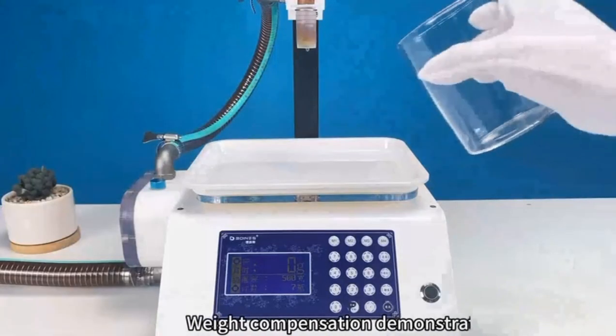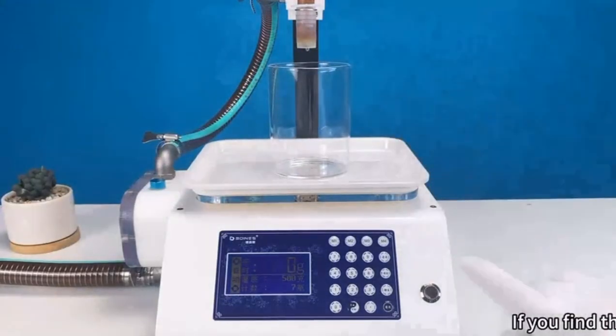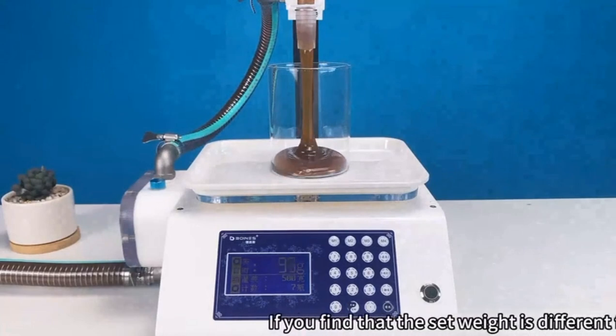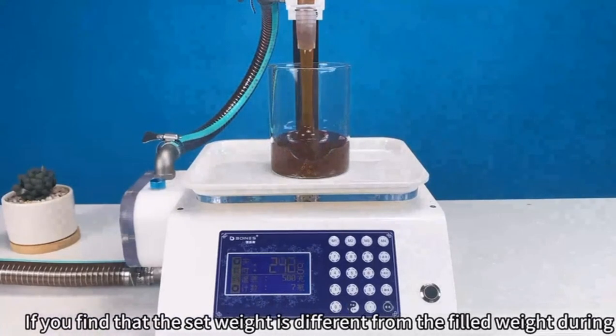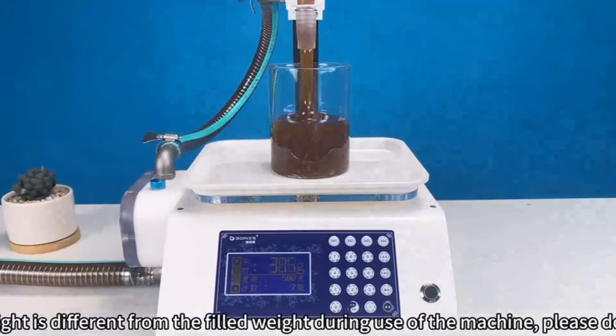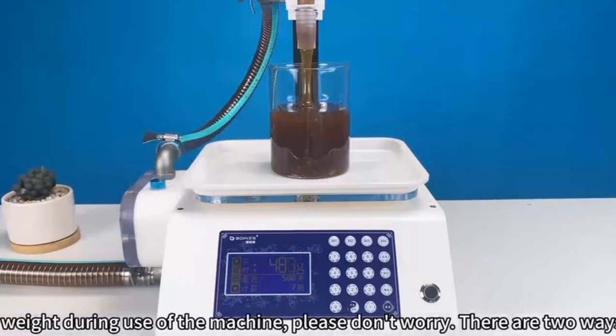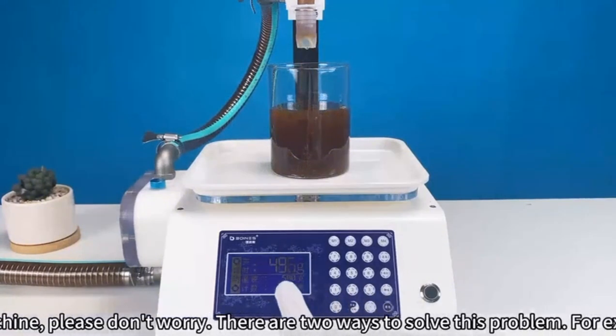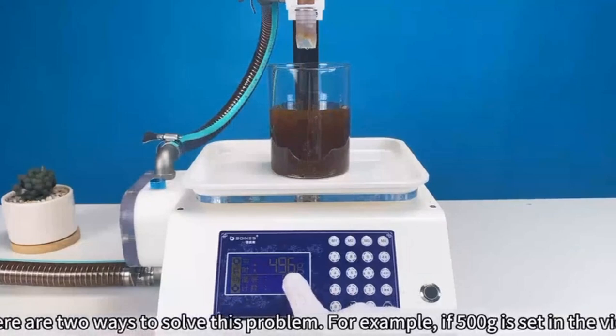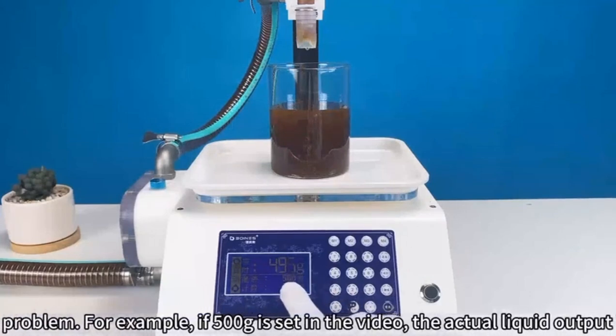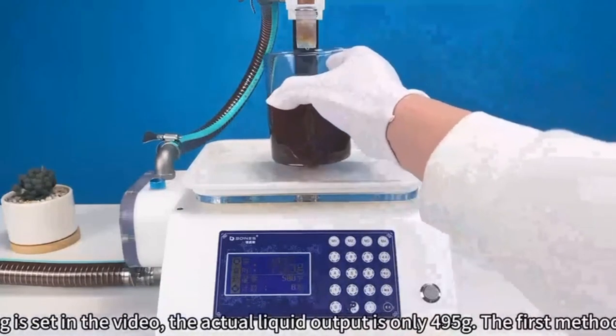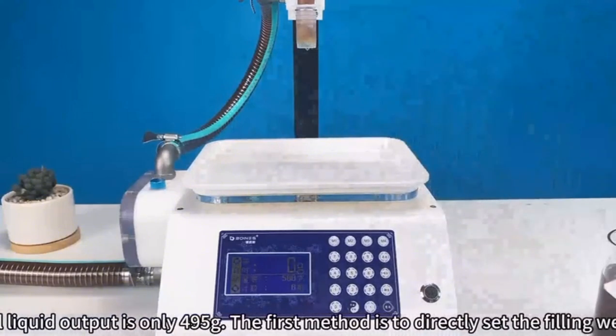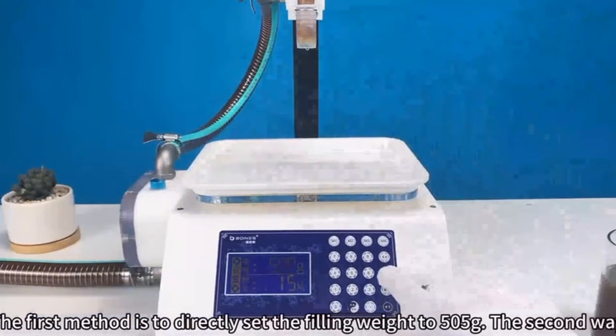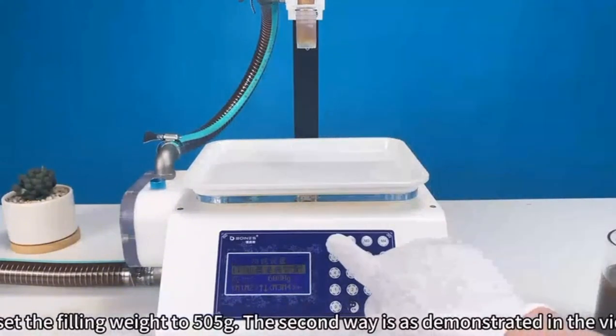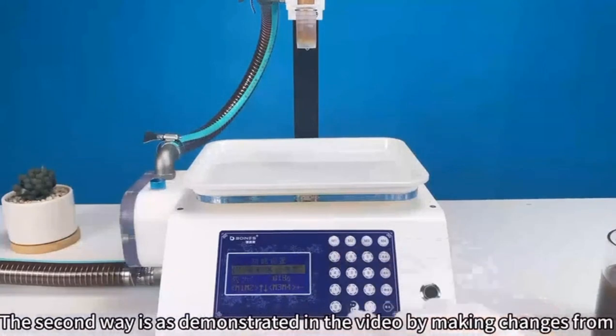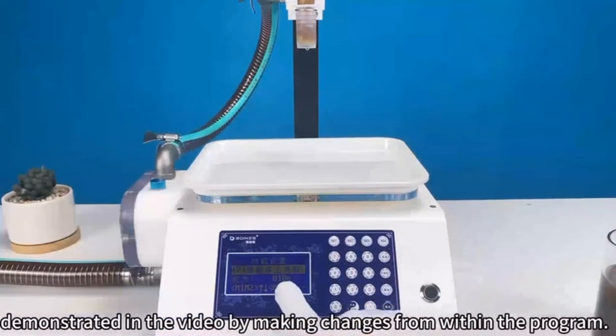Weight compensation demonstration. If you find that the set weight is different from the filled weight during use of the machine, please don't worry. There are 2 ways to solve this problem. For example, if 500 g is set in the video, the actual liquid output is only 495 g. The first method is to directly set the filling weight to 505 g. The second way is as demonstrated in the video by making changes from within the program.